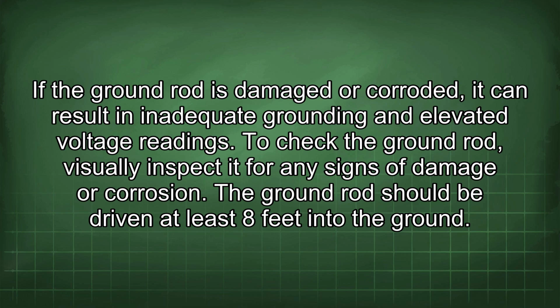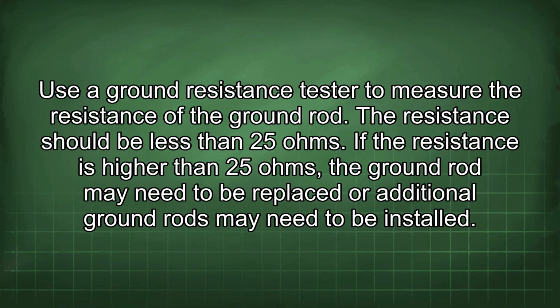The ground rod should be driven at least 8 feet into the ground. Use a ground resistance tester to measure the resistance of the ground rod. The resistance should be less than 25 ohms. If the resistance is higher than 25 ohms, the ground rod may need to be replaced or additional ground rods may need to be installed.